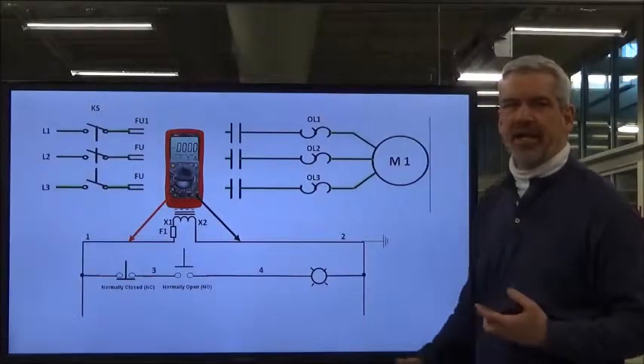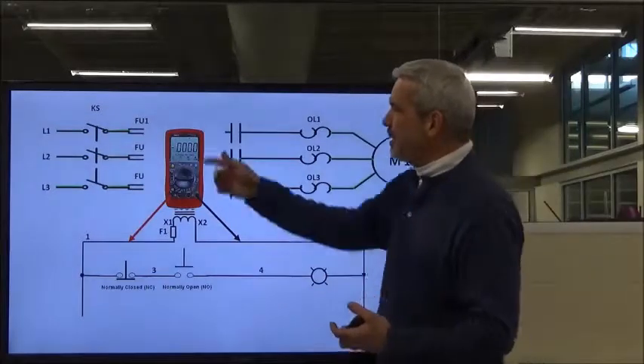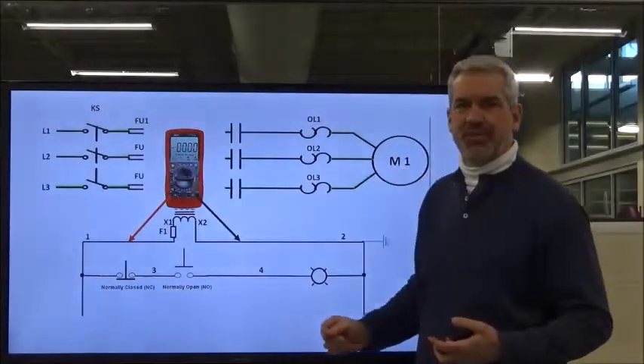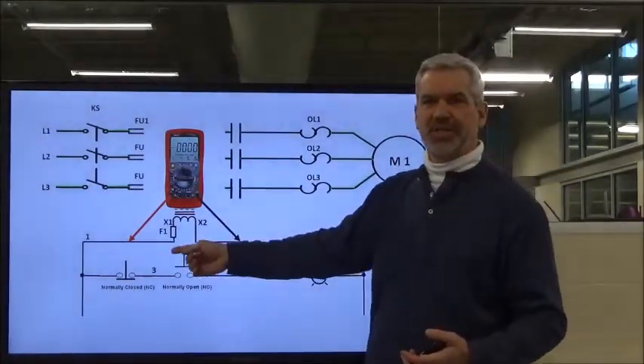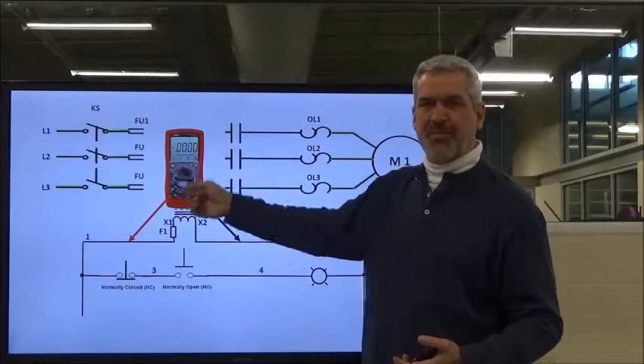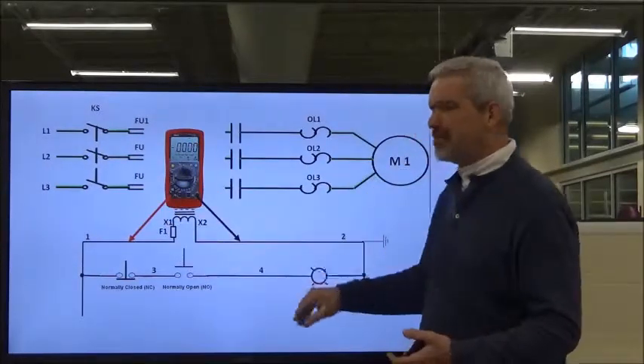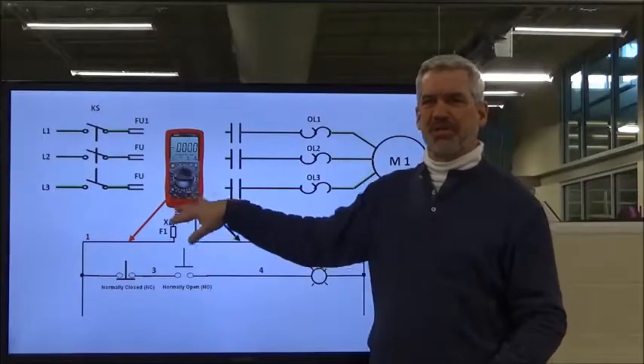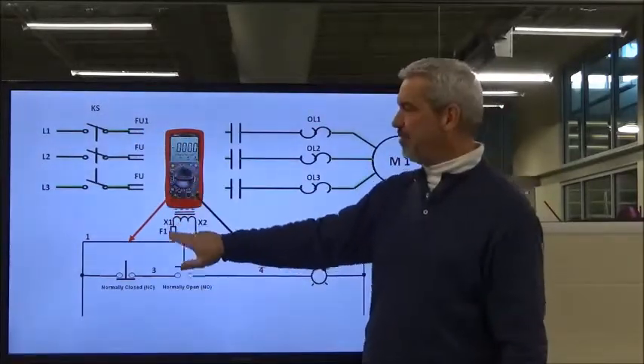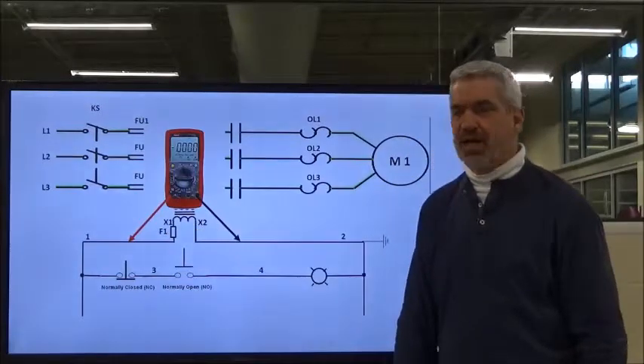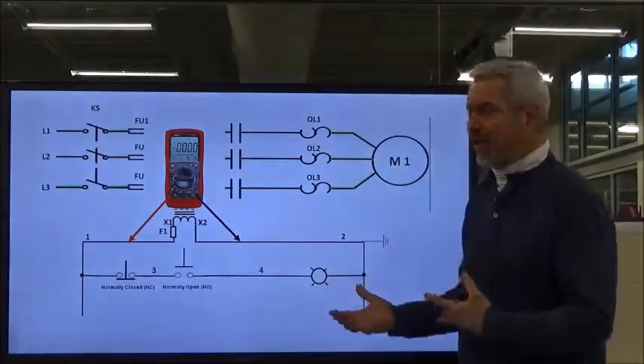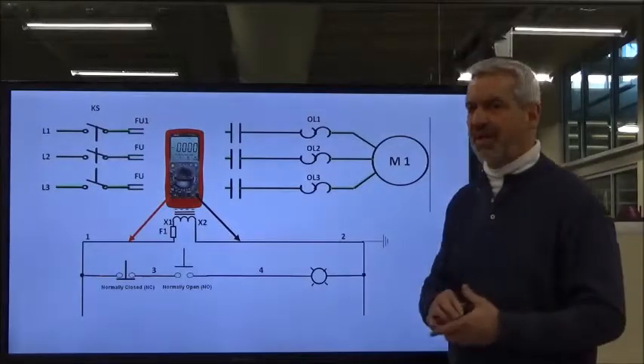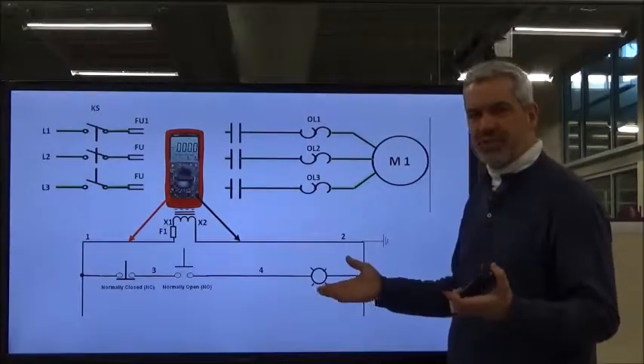So immediately, if I walk up and, say I had that pilot light and it worked, well, I'm not going to go check the primary voltage of the transformer because I'm getting secondary voltage. I couldn't get secondary without primary. So I know the primary is good, I know the secondary is good because I got a light. So I'm not really going to focus too much on the transformer, not on three-phase fuses, the fuses to the primary, or the fuse coming out of the secondary. I know I've got voltage just by looking at it. So I used a little common sense there, with just what's given to me right here.